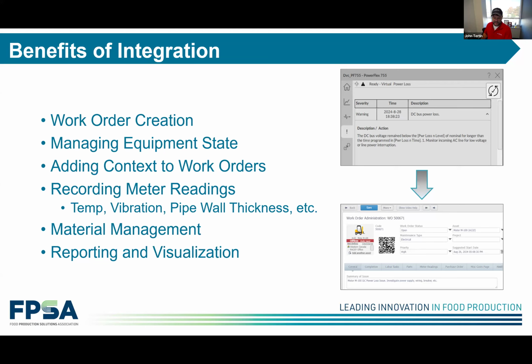Beyond meter readings, you can provide other context to a work order, such as the timestamp of failure for a specific device, or the state the equipment was in at the time, like a milk separator reporting a failure during a desludge operation. You can record the state of the equipment when something occurred, and even support operator comments. If my SCADA system lets an operator bring up a faceplate for a device, there can be a button that just says send a message to maintenance, without needing to create a full work order, just contextual information about that asset. That context is so rich and deep that it becomes extremely powerful.